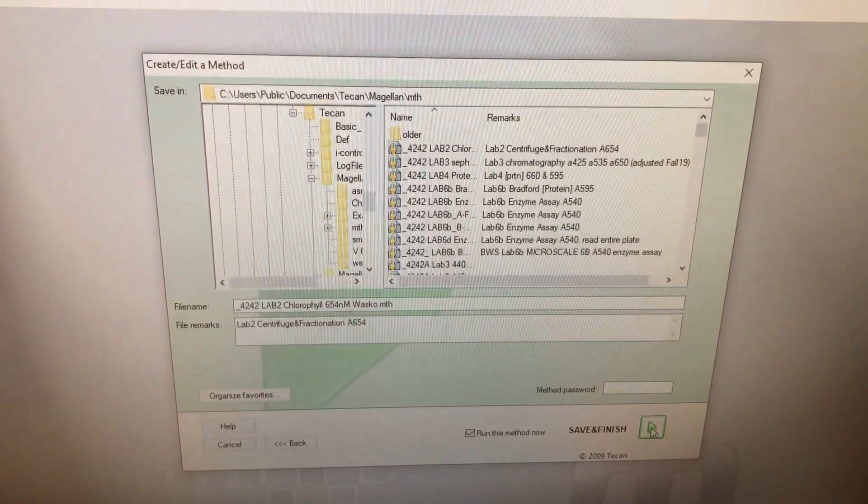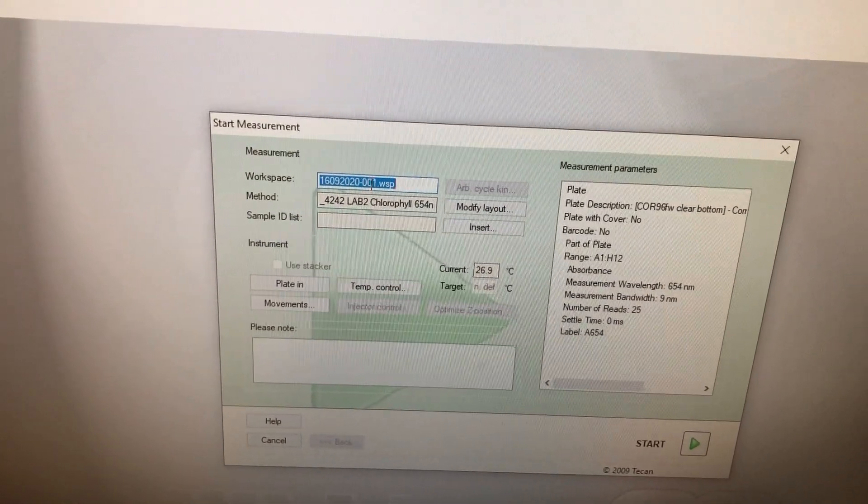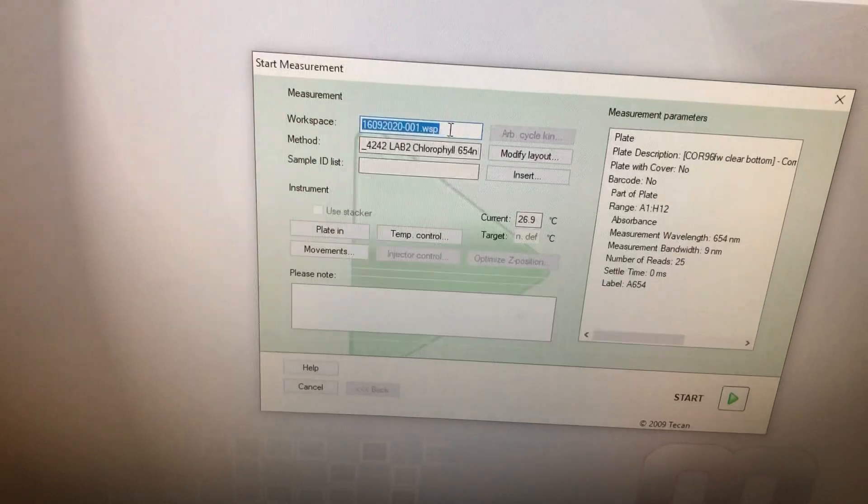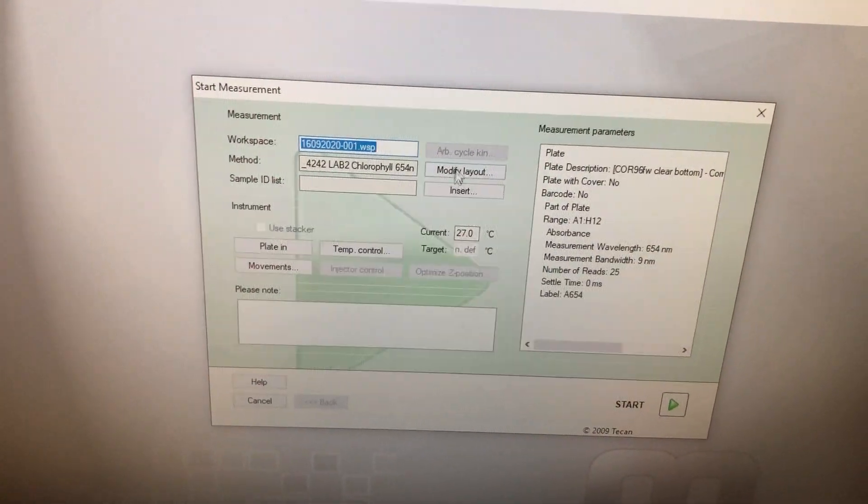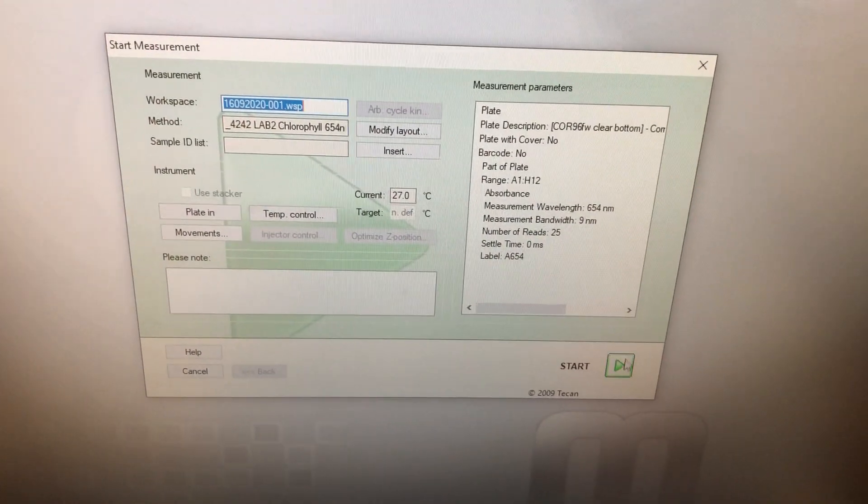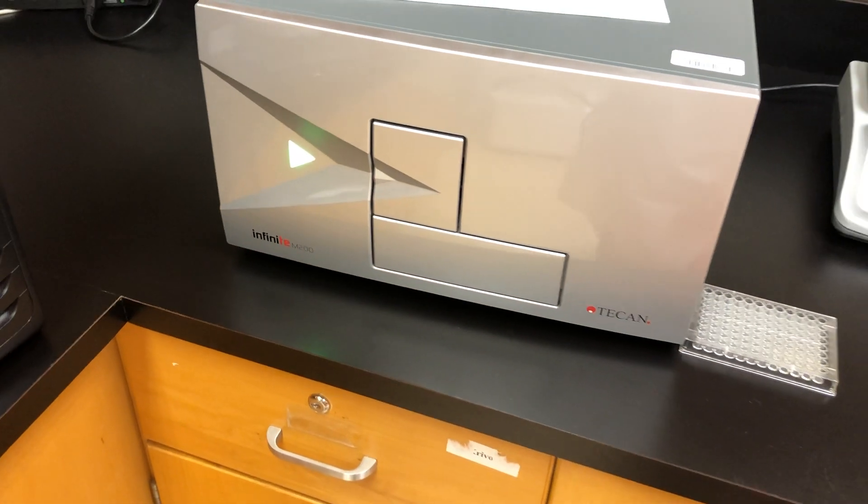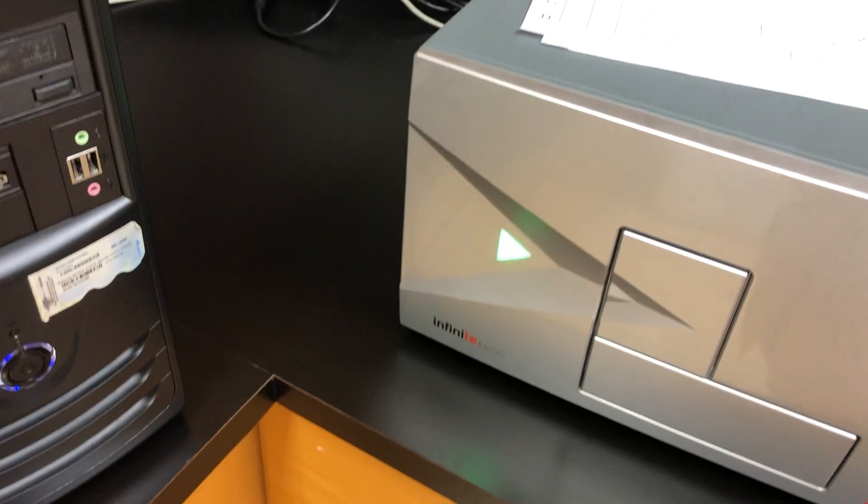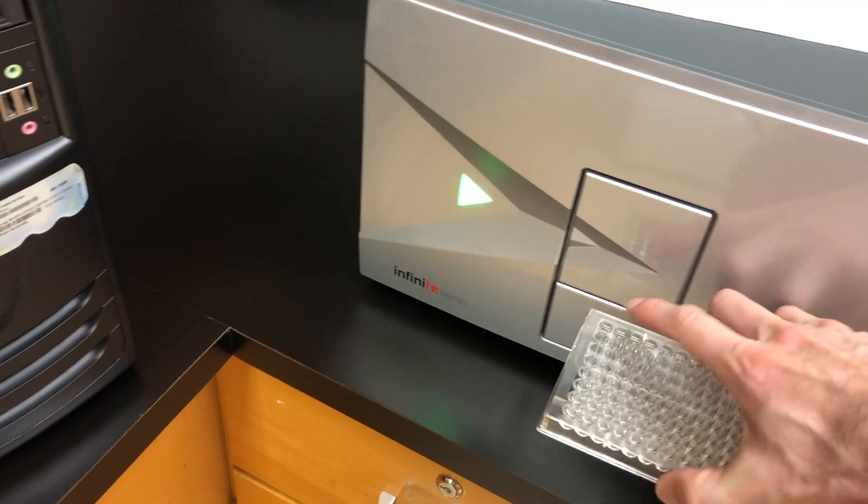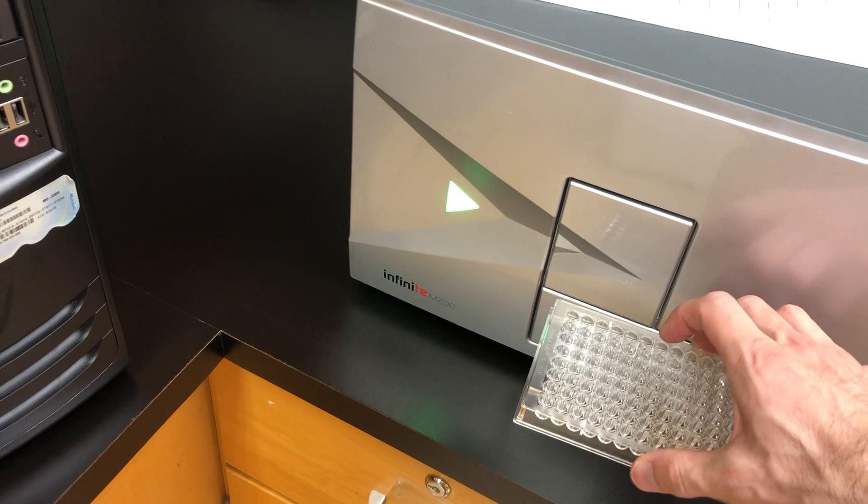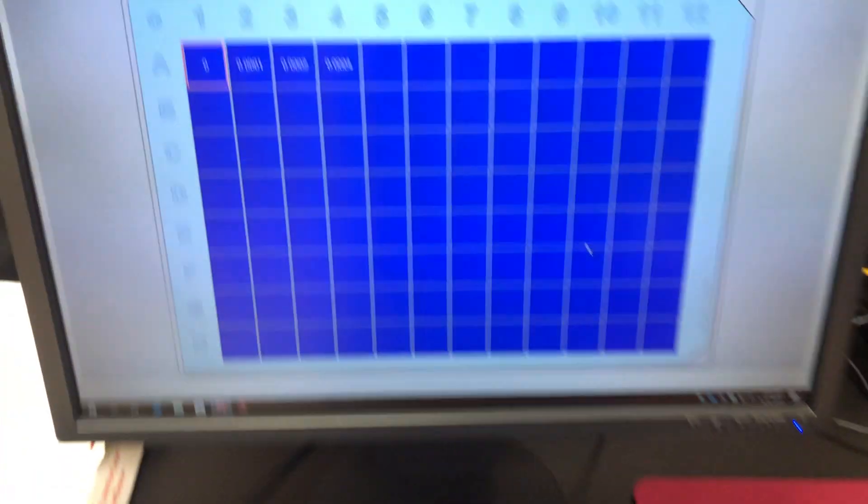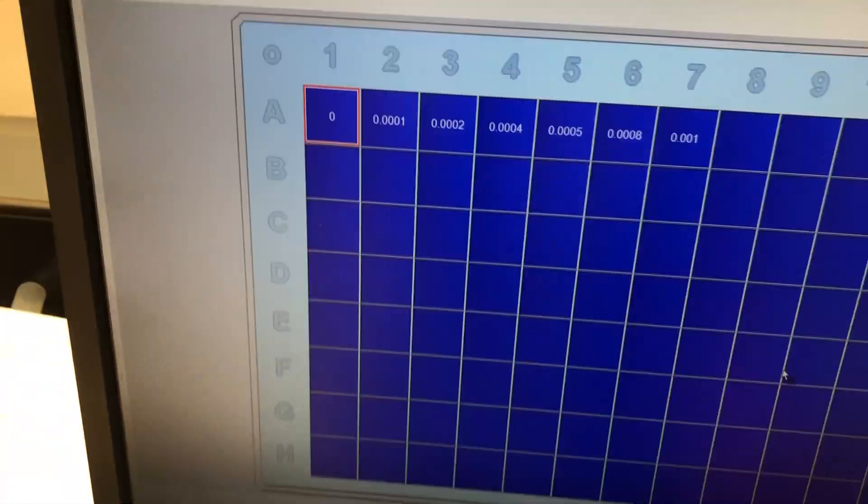And then it'll ask you to save the protocol if you've made any changes. And just click Save. Now it's asking us to save the file. This is, we'll just save an internal file for this software. I usually just leave this default. And once you do that, you just press Go now. It's pulled in the plate. Like I said, I didn't put a plate in there, but if you put a plate in there, you just set it down with A1 at the top left. And it just sits in there pretty straightforward. And now it goes through and takes all those reads.